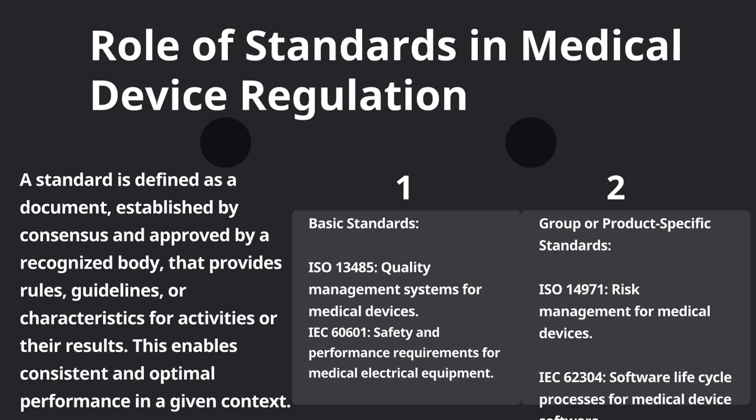The typical basic standards are ISO 13485, Quality Management Systems for Medical Devices, and IEC 60601, Safety and Performance Requirements for Medical Electrical Equipment. A product-specific standard is like IEC 62304, Software Life Cycle Processes for Medical Device Software.